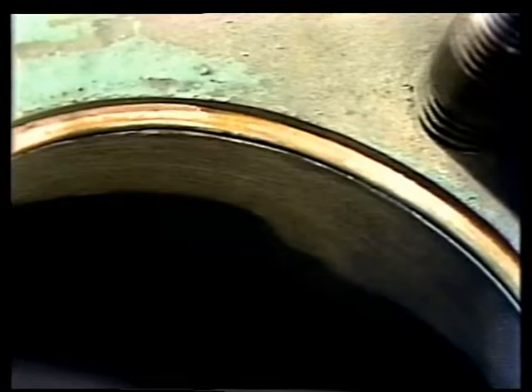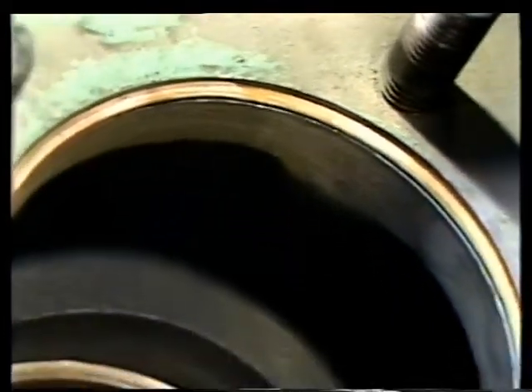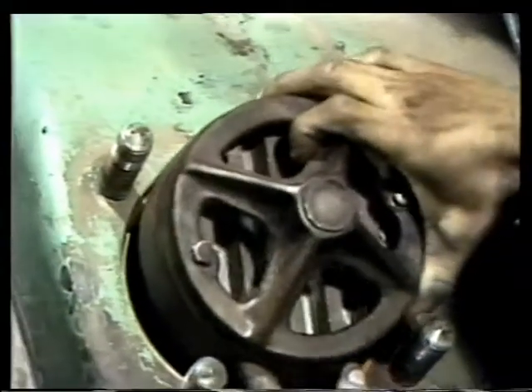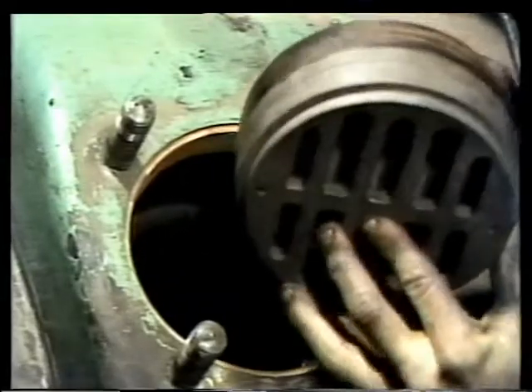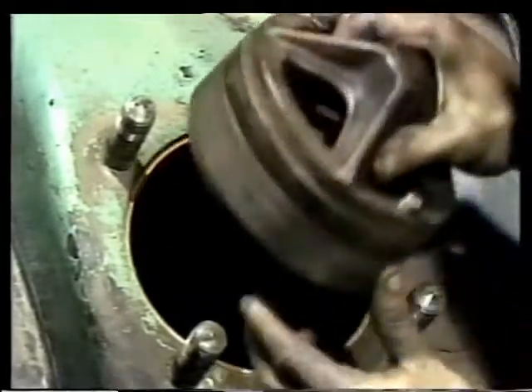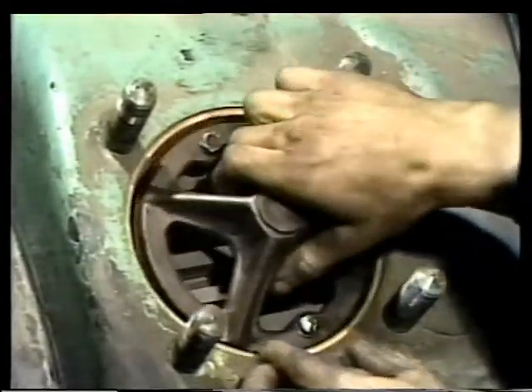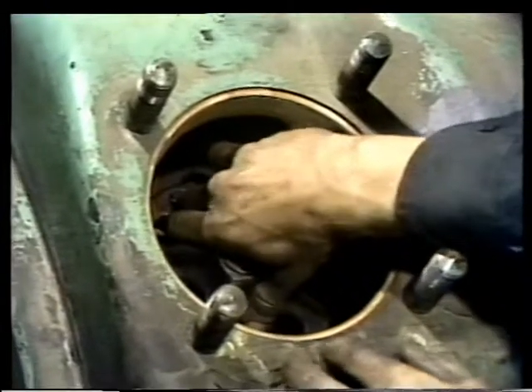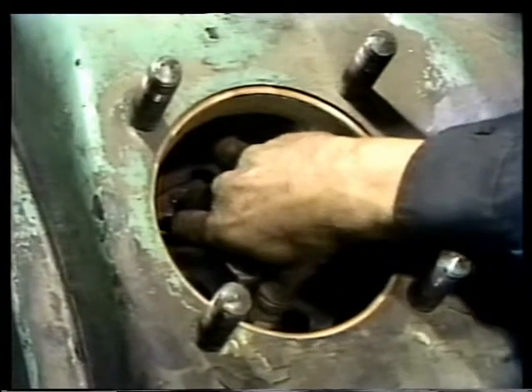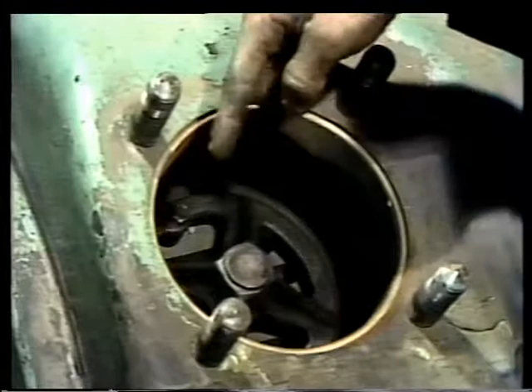When placing the valve into the casing, make sure that the inlet valve goes into the inlet port. If you make the mistake of putting the inlet valve into the discharge port, the valve won't work, and it could cause excessive pressure that would damage the valve and piston rings.